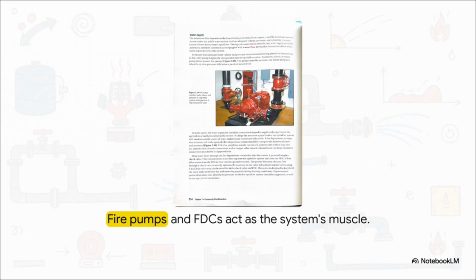Now, sometimes the municipal water supply just isn't strong enough on its own to provide the required volume and pressure, especially if a massive multi-story fire breaks out. To make sure pressure is maintained, an electric, diesel, or steam-powered fire pump is incorporated into the system, and it kicks on automatically the second system pressure drops. Also, if you look on the outside walls of commercial buildings, you'll almost always see a fire department connection, or FDC. This is essentially a giant Siamese inlet. A fire department pumper truck can roll up, connect its heavy hoses directly into this FDC, and physically pump extra municipal water and extreme pressure right into the building's own sprinkler system to support it. It's essentially plugging a supercharger right into the building.